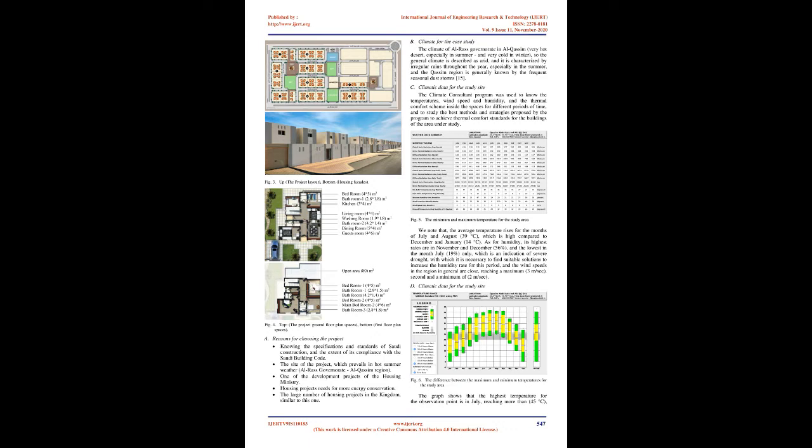There are several types of nano composition, the most important of which are vacuum insulation panels, VIPs. These panels are characterized by large thermal insulation, with a thin thickness of 8 to 35 mm, and the coefficient of thermal conductivity of them reaches 0.0035 W/m.K at 25 degrees. It is 5 to 10 times less than traditional insulation materials, and its lifespan ranges from 30 to 50 years, and it also does not require regular maintenance.